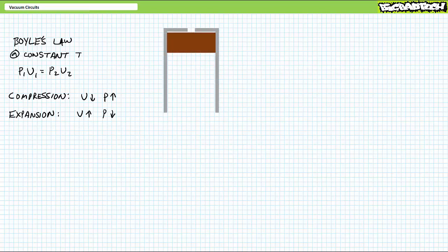Consider an open-end cylinder with a piston at the top at atmospheric conditions. If the piston is pulled forcefully downward, volume in the cylinder increases and pressure in the cylinder decreases. When we start at atmospheric conditions, any increase in volume and consequent reduction in pressure makes the expanding cylinder a vacuum or less than atmospheric conditions. Environmental air outside the cylinder at atmospheric pressure is pulled into the less than atmospheric cylinder. What I've described is a suction action of a reciprocating compressor.